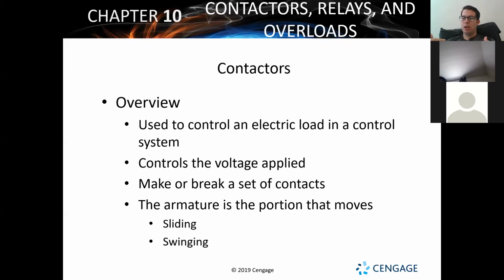It's just like we would have with a switch. When we practiced with switches on resistance, and you guys saw that, if the switch is in an open position where it's disconnected, it's going to read OL or infinity. If it's in the closed position, it should read close to 0, or a very, very low amount of resistance. The problem with a contactor is that when it's normally operating, there's going to be power present. So that's the biggest difficulty with it.